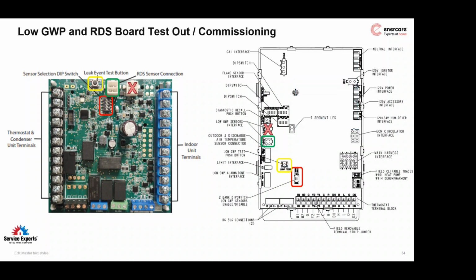So on each of these control boards, you can see highlighted in yellow that there is a test button or leak event button. So in order to test, first we have to force the equipment into a cooling call. Let it get to a point where it's stabilized, the fan's running, the refrigerant pressures are operating normally, and simply push that test button one time and then release it. What should happen if this is set up correctly is the air conditioner outside, after a short period of time, if not immediately, should shut off. So the compressor should stop running, the outdoor fan should stop running. And the indoor fan blower should move to the cooling speed that you've set up for fan only.